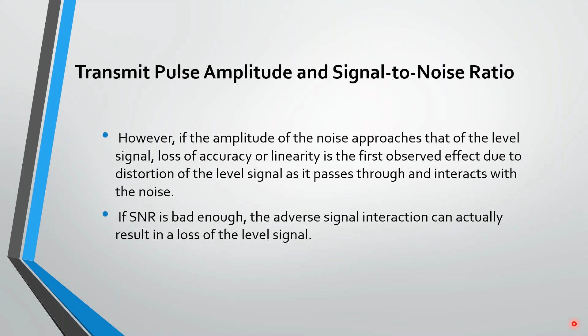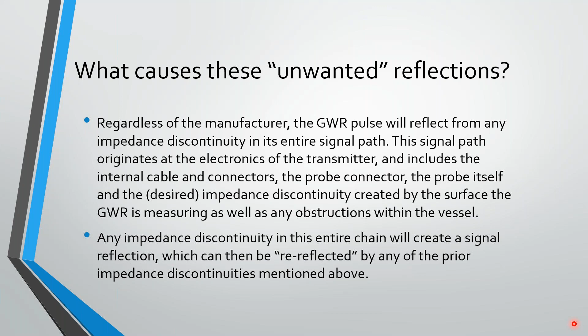So what causes unwanted reflections, or noise? Well, a lot of things. The cable connectors, if they're not the proper type, the probe connector itself, the probe itself, if we didn't use the right type of probe and we have some impedance discontinuity within the vessel, obstructions within the vessel, all of these can re-reflect any of these bad signals. And things just start bouncing, right? So a signal gets reflected, bounces off another device like an agitator or maybe a ladder that's in there, and it gets re-reflected. If you've ever accidentally put something with aluminum foil in your microwave and turned it on, you'll know exactly what I mean by re-reflected. These are the kind of things we're talking about here. So how do we avoid problems?